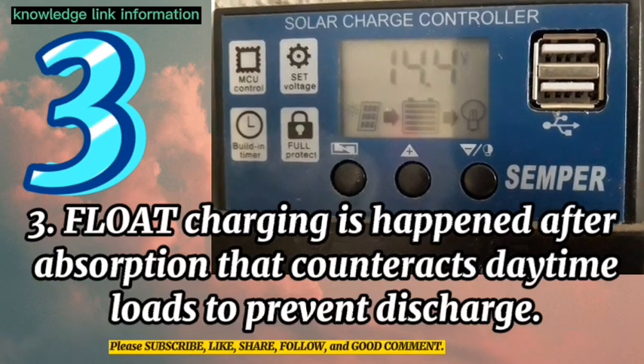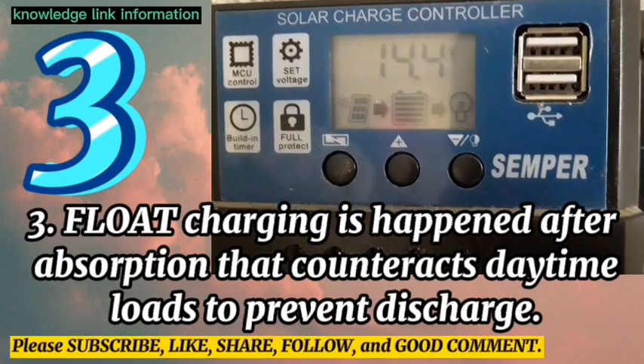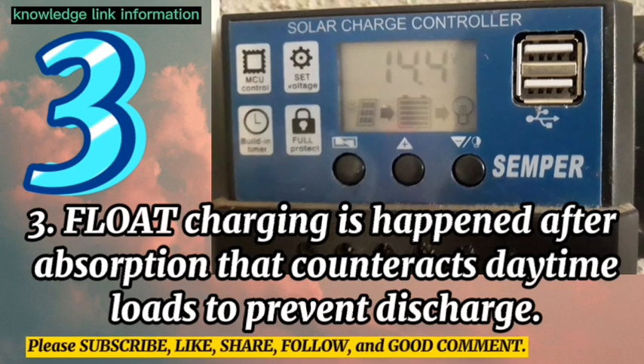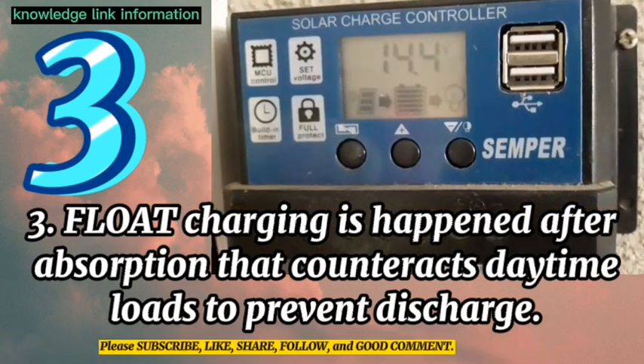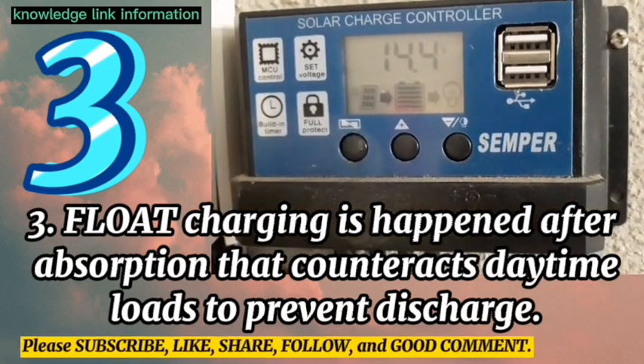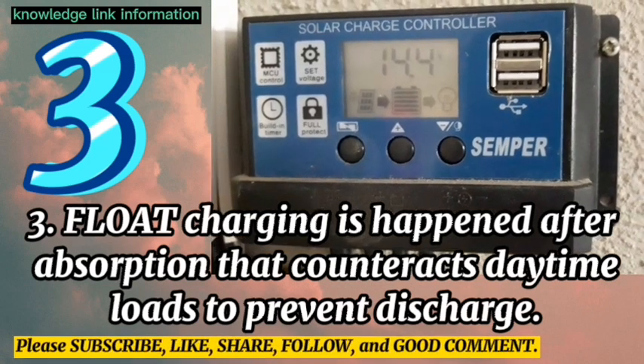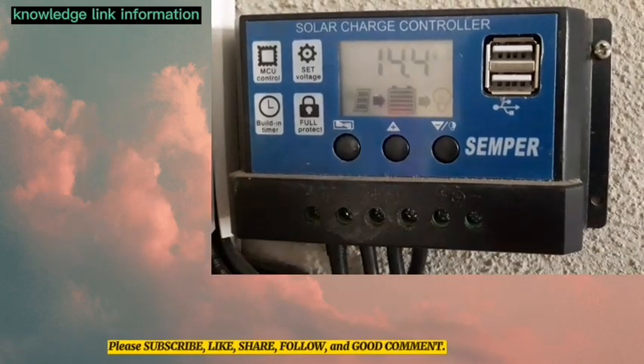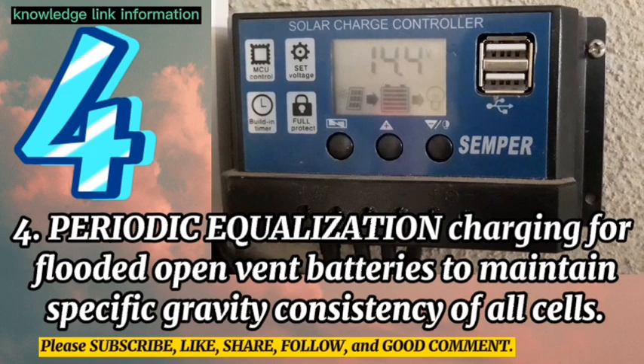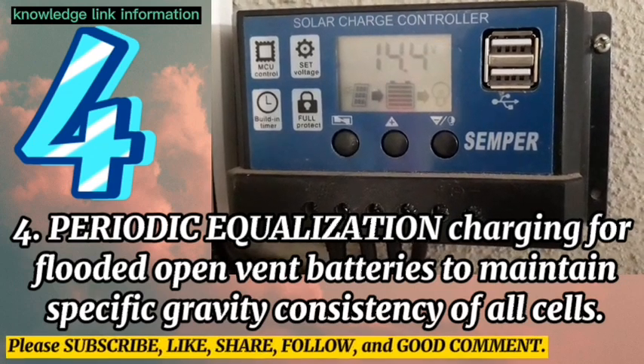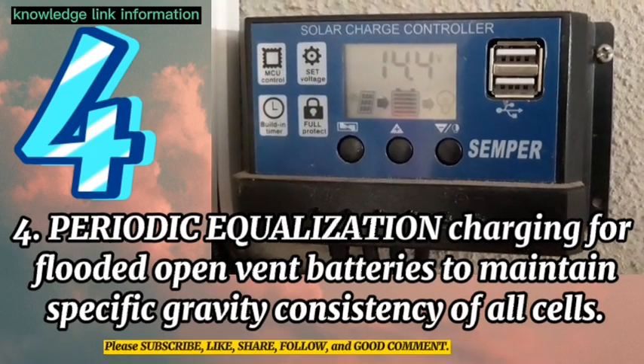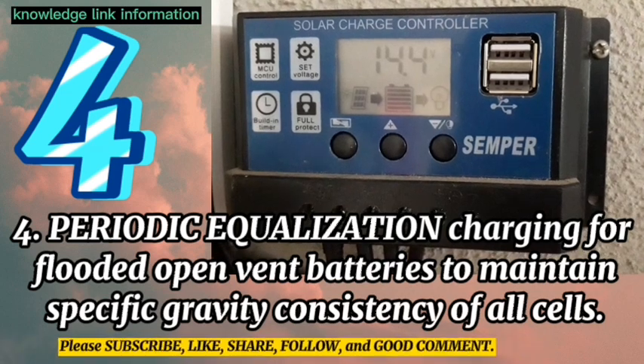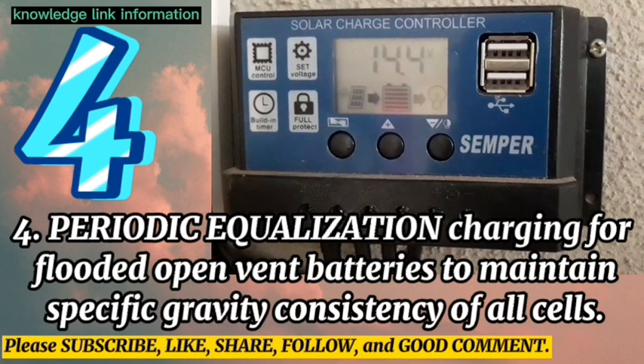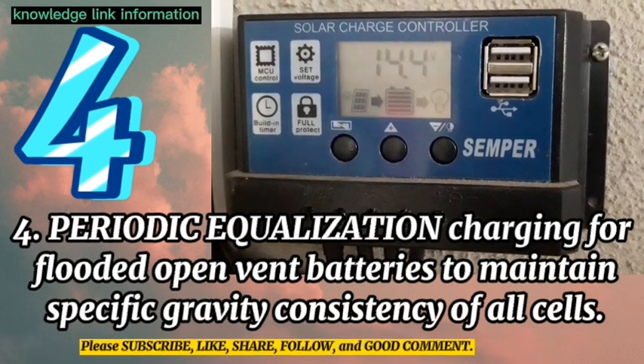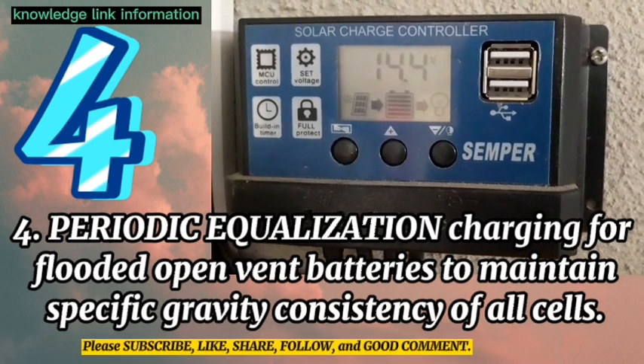Number 3. Float charging happens after absorption and counteracts daytime loads to prevent discharge. Number 4. Periodic equalization charging for flooded open vent batteries to maintain specific gravity consistency of all cells.